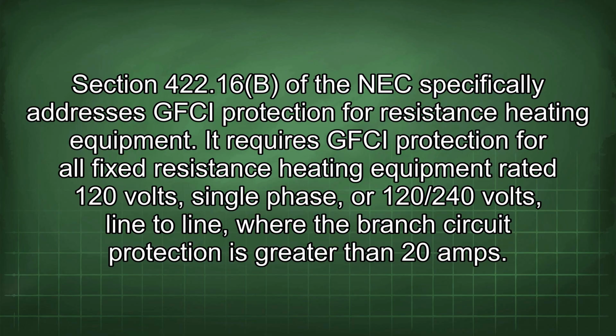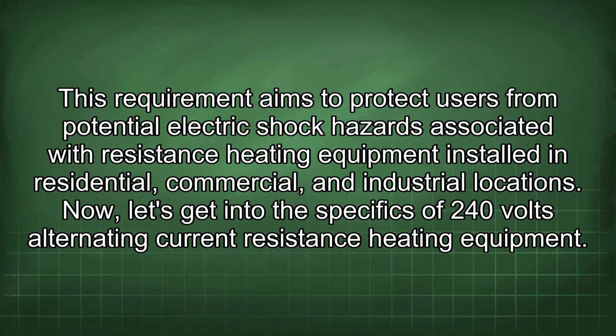Section 422.16(b) of the NEC specifically addresses GFCI protection for resistance heating equipment. It requires GFCI protection for all fixed resistance heating equipment rated 120 volts, single phase, or 120/240 volts, line to line, where the branch circuit protection is greater than 20 amps. This requirement aims to protect users from potential electric shock hazards associated with resistance heating equipment installed in residential, commercial, and industrial locations. Now let's get into the specifics of 240 volts alternating current resistance heating equipment.